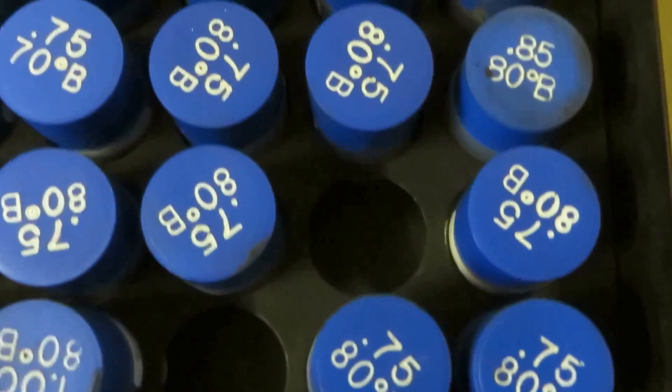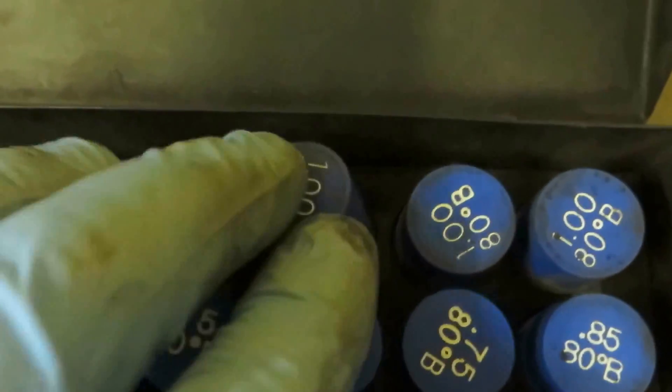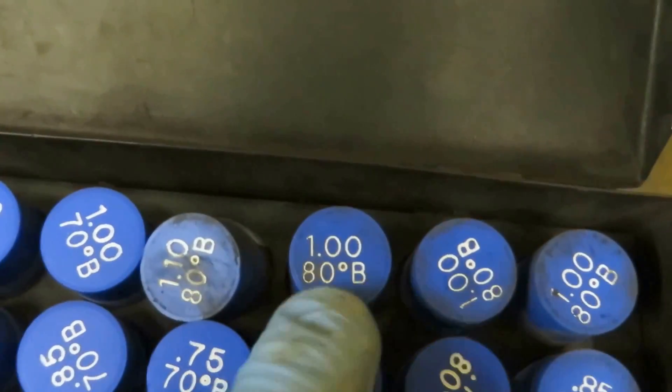Just some of my different models that I carry in the truck for residential work. 75, 80s are common. 85, 80s, one gallon 80s. These are Delavan nozzles. You got A, which would be a hollow nozzle, you got B, which is semi-solid, and then you got solid nozzles. I usually run semi-solid nozzles myself.